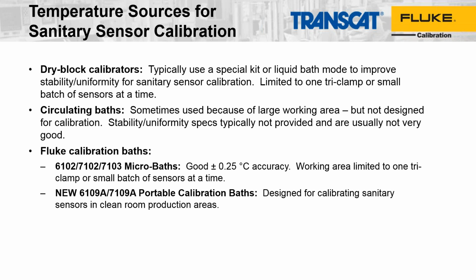So first, we're going to talk about temperature sources a little more specifically, what the different types are that we typically see being used. A very common type is the dry block calibrator. This is often referred to as a furnace, or a calibration furnace, or a dry well. They're called dry block calibrators because typically they don't use any fluids. There's just a metal block with holes machined into the block that will accommodate temperature probes that can be inserted into the block or the insert.